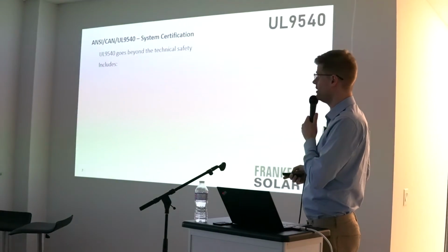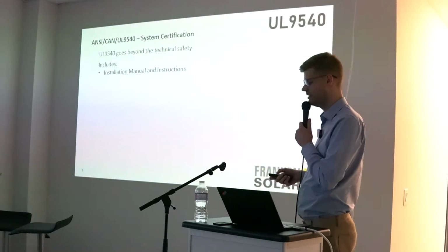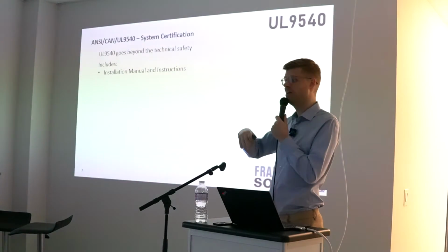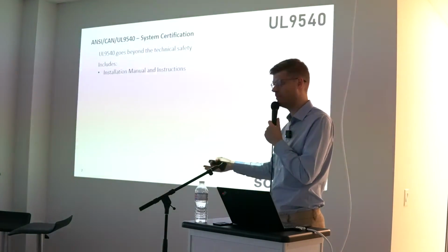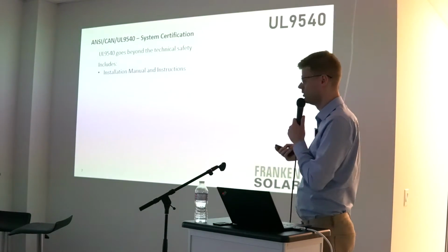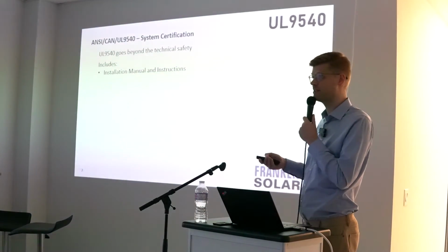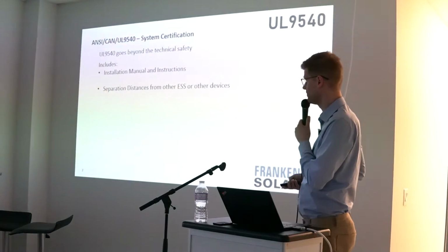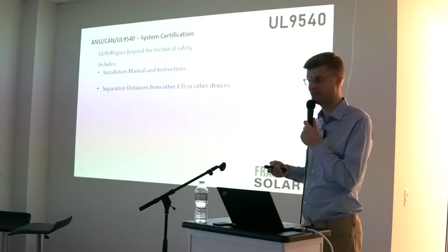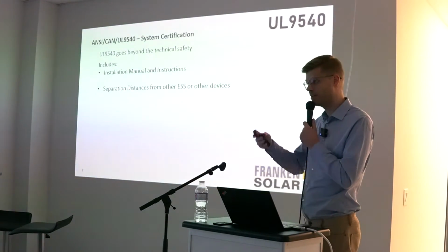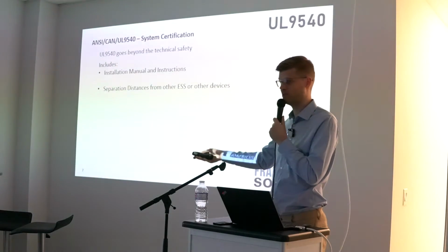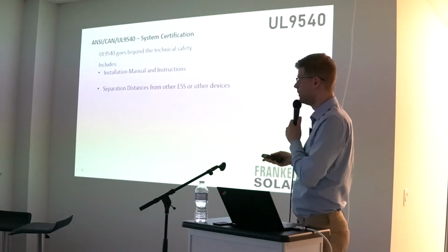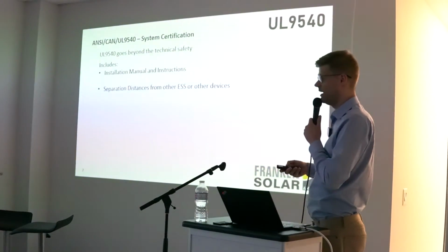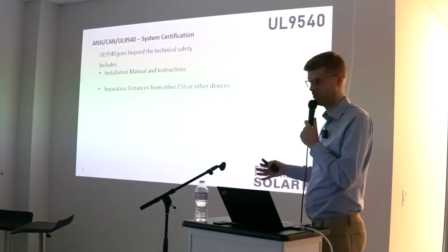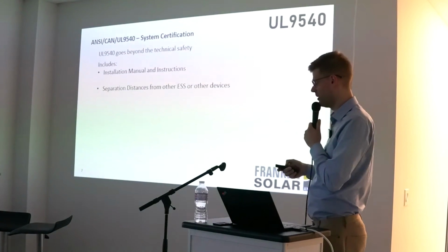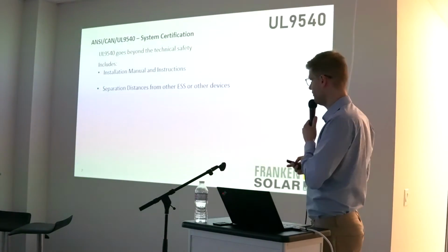UL 9540 goes beyond just the technical compatibility. For example, it tests, of course, the inverter and the battery interaction. How does the battery protect itself? How does it communicate with the inverter, for example, to be safe in operation? But it also includes documentation of how you install these systems and what things you have to pay attention to. It also specifies certain separation distances, what capacity can be installed in one increment, and how you can co-locate multiple of those storage systems to achieve more power or more capacity together. Most of the time it's an energy limit just from a fire safety standpoint, so that you do not have all critical components lumped into a big pile of equipment, but you can separate them and therefore have lower risk by physical separation.